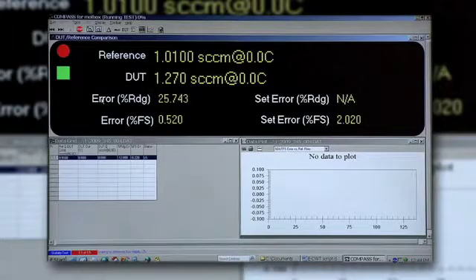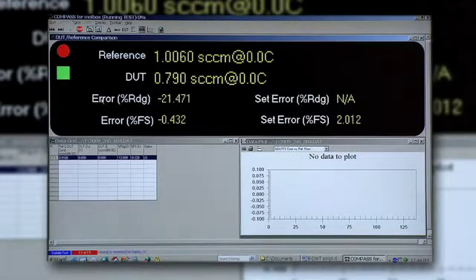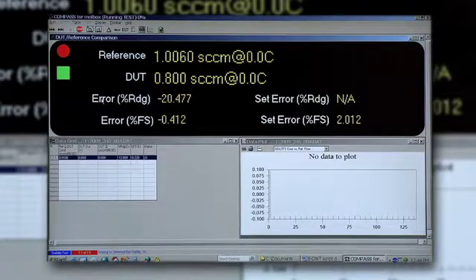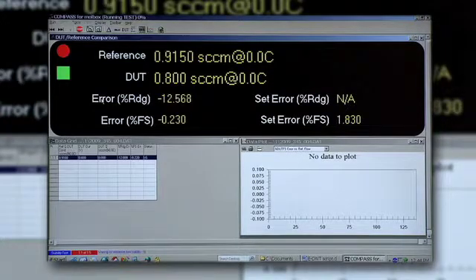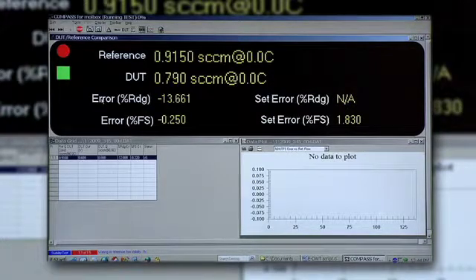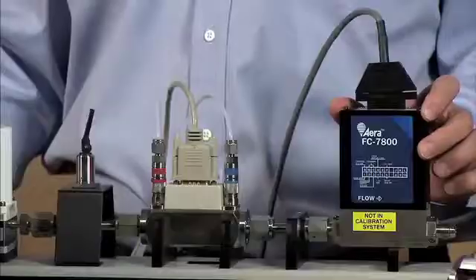The test has now begun. This is a five-point test running from zero flow up to the maximum or full-scale set point of the mass flow controller.